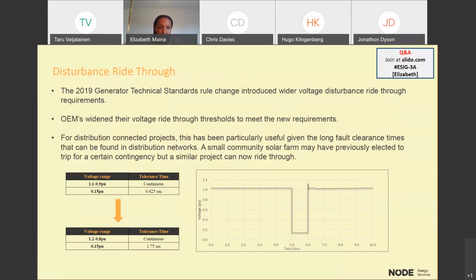And some of the benefits we've started seeing from that change: a project that, for example, connected maybe 5-10 years ago would potentially not have been able to ride through some of the faults that we see at the distribution level. Distribution level projects sometimes have to deal with long duration faults. Whereas in transmission we're talking milliseconds, distribution can see some faults in the order of seconds. Historically, we would have to do some analysis to see how these projects would go, and based on the capability at the time, some of these projects would then elect to disconnect for that particular fault.